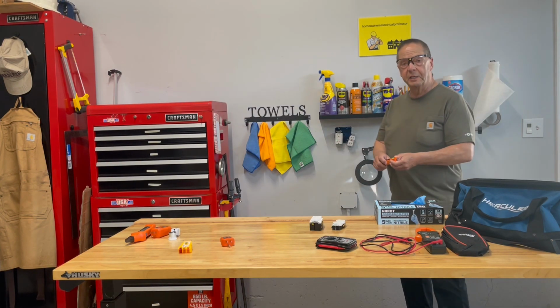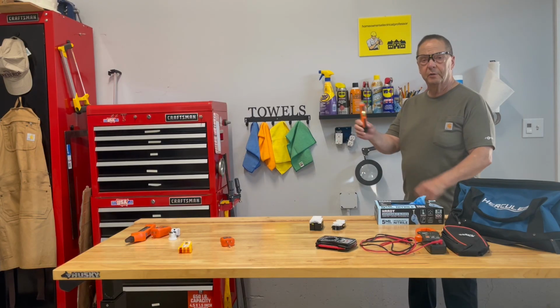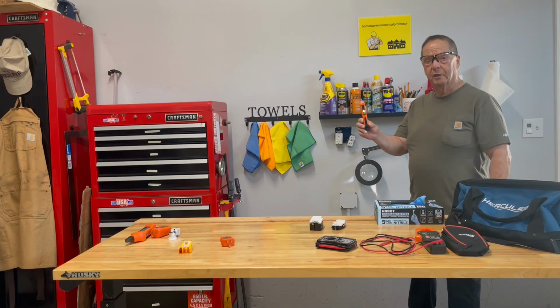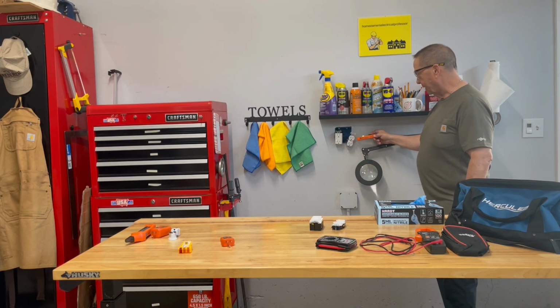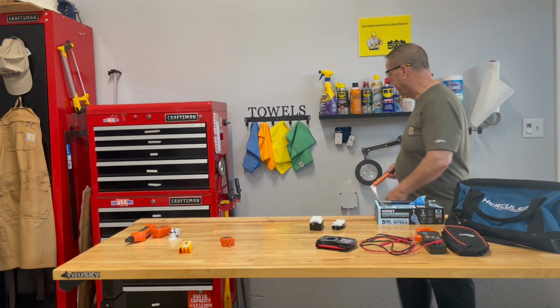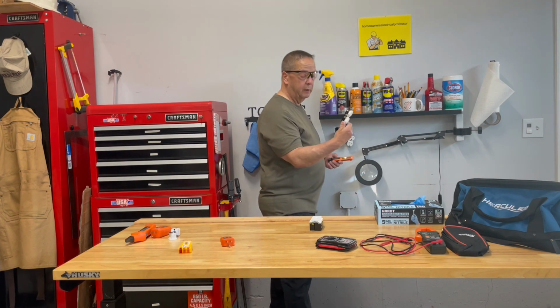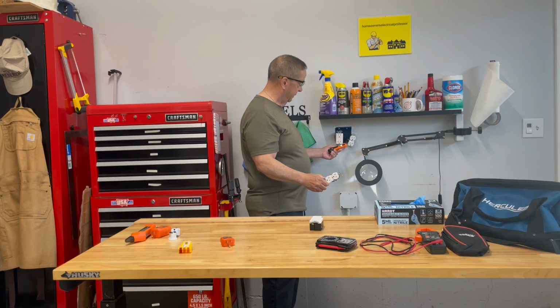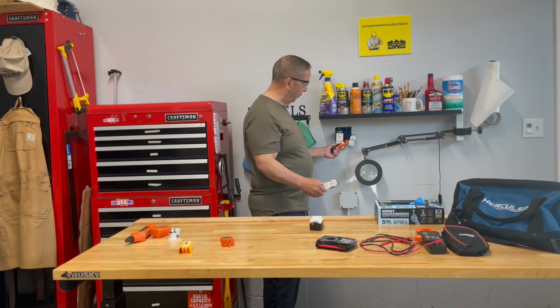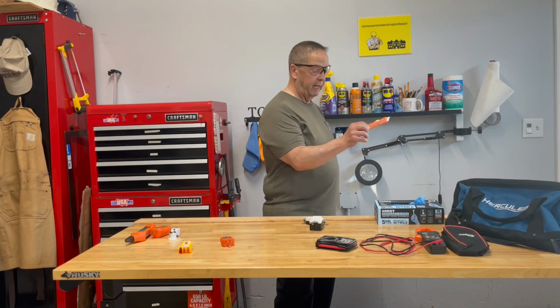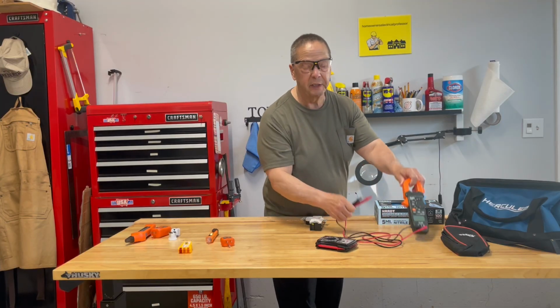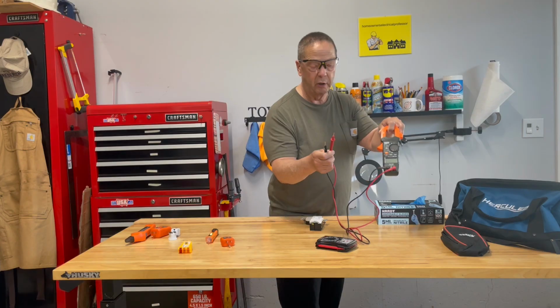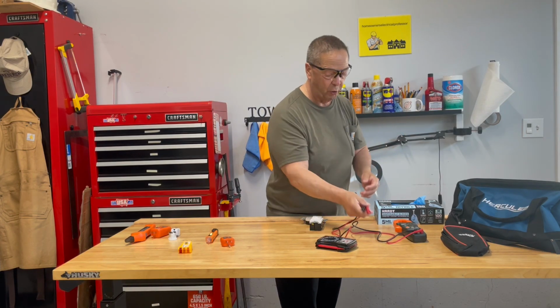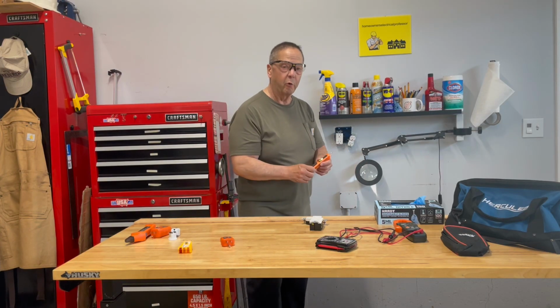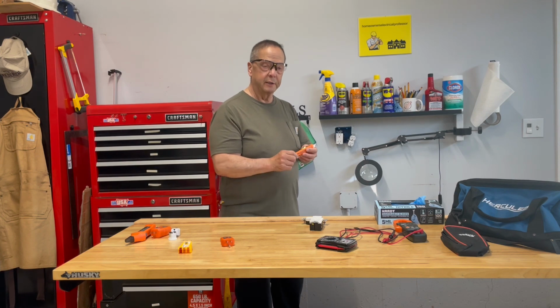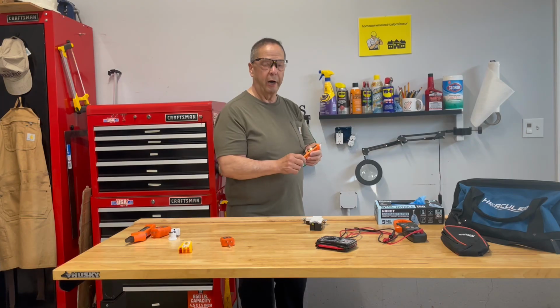Now I'd like to demonstrate use of the non-contact voltage tester. Remember, this only tests the presence of it. It's not going to tell you the quantity involved. So here's my black or ungrounded conductor, and it goes off. When I go to the other side of the receptacle, the neutral and the green grounding side, as you can see, I don't get any voltage there. Now, the reason it's a non-contact, this is all plastic, as opposed to later on when we get into these meters that can measure the quantity also. Now you have to get in close and touch the terminals themselves. This is a lot safer for homeowners. Later on when I get into opening up switch boxes, sometimes you'll need to identify what is the hot or the feed wire that comes into the box. That will be later on.